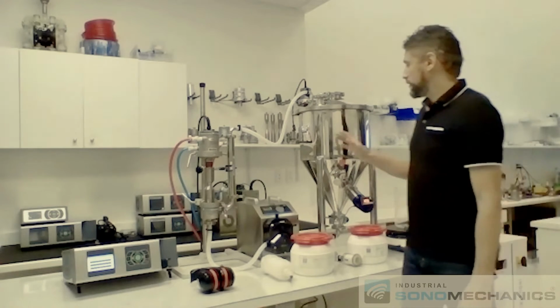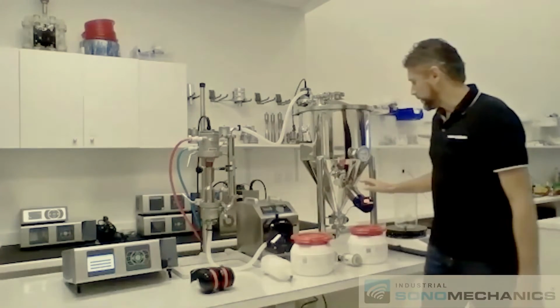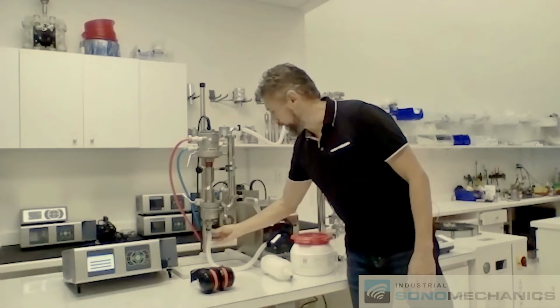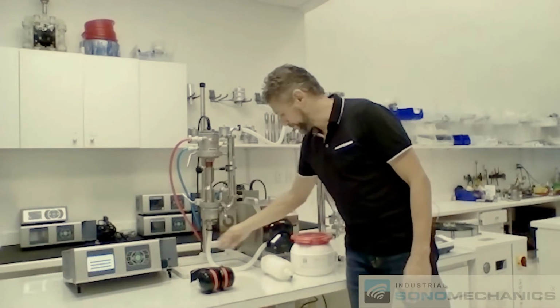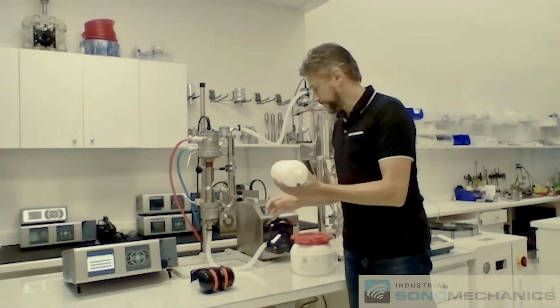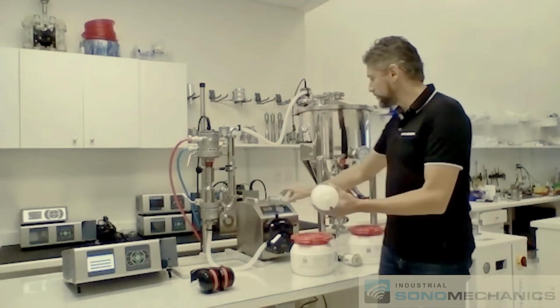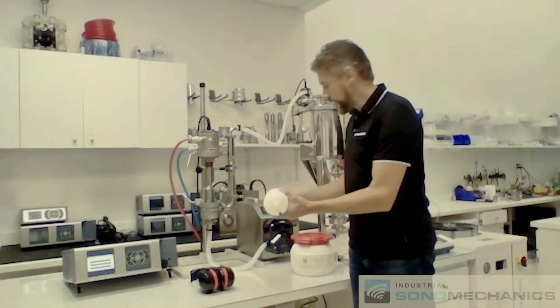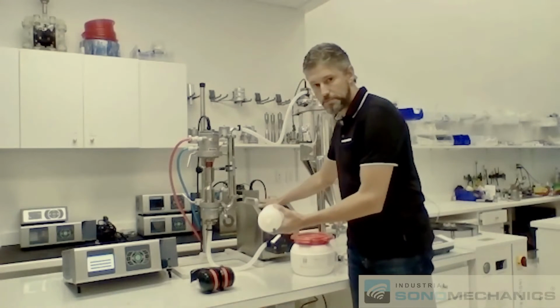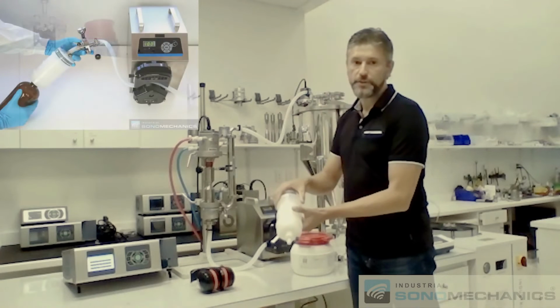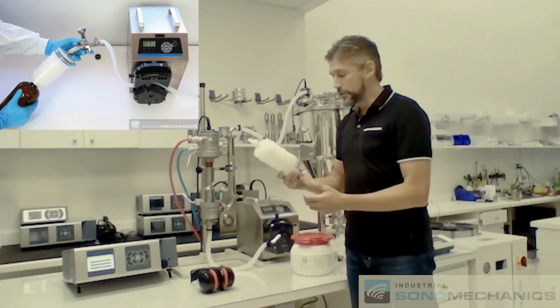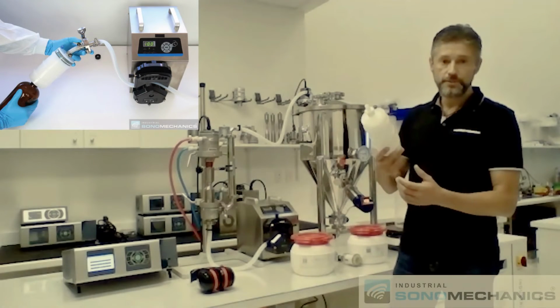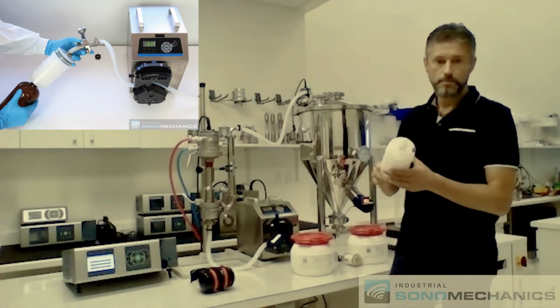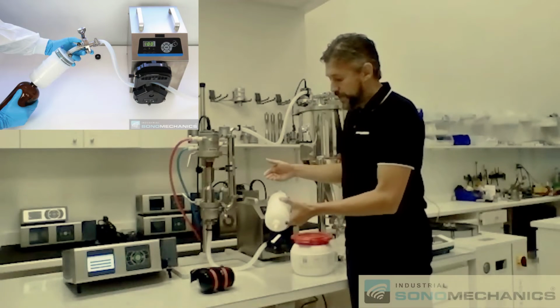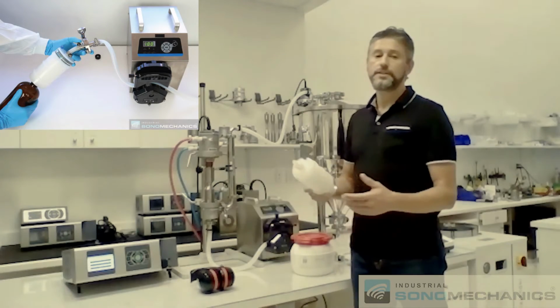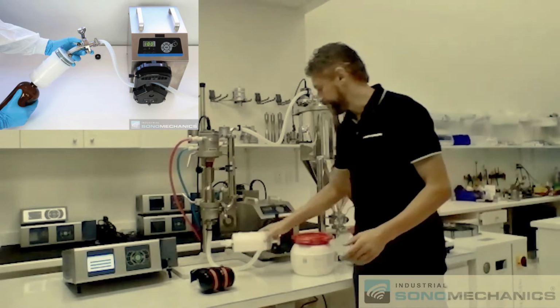you have to do. So once the process is done and you've collected all your liquid here, you will disconnect the line from here. You will connect it to this filter. You'll again reverse the flow and slow it down. And then you'll just pass all of this liquid using this pump through this filter into your finished product container. The filter is there to sterilize your nanoemulsion. This is a sterilizing filter, 220 nanometer pore size. Once the liquid passes through this filter, it's sterile. You collect it in the finished product container, and you're done.